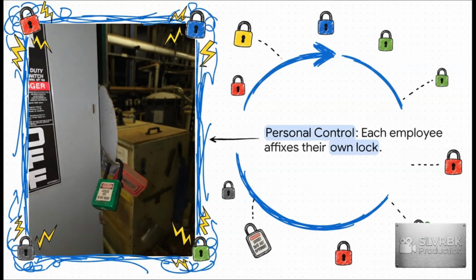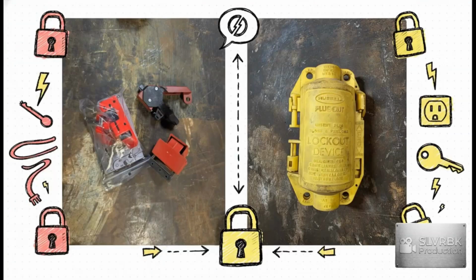Every authorized employee puts their own distinct personal lock on a group lockout mechanism, like a hasp. When you finish your specific part of the job, you take your lock off, and the machine literally cannot be re-energized until every single person has cleared out and removed their personal lock. Now, your teams might use different hardware depending on the energy source, like circuit breaker lockouts on one hand, or maybe a bright yellow cord end isolator on the other. But the underlying principle, totally identical. It's your lock, your life.